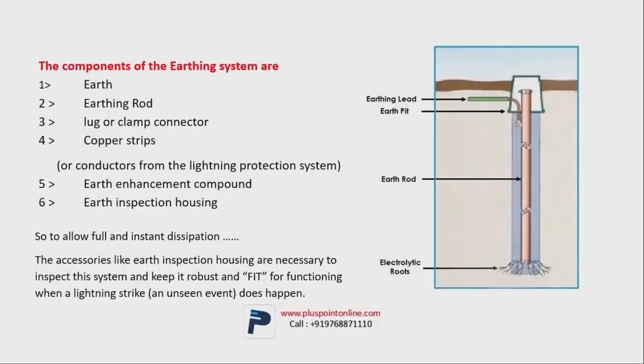If I talk about the earthing in detail, there are a few components of the earthing system as well. The earth, as in the soil, needs to be good. The earthing rod is a copper rod which helps in earthing. Lugs and a few cables are attached to the rods. Copper strips are attached through which the earthing can be done at a distance. In the lightning protection system, we saw that the earthing gets conducted in these copper strips.